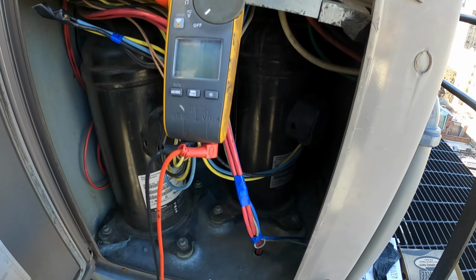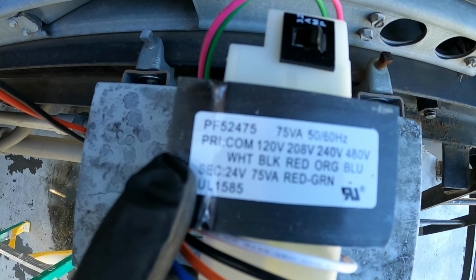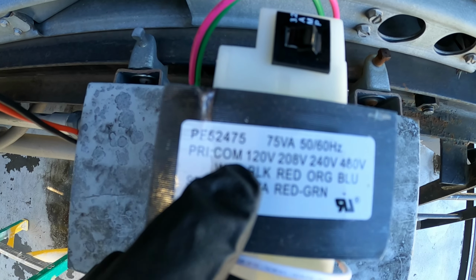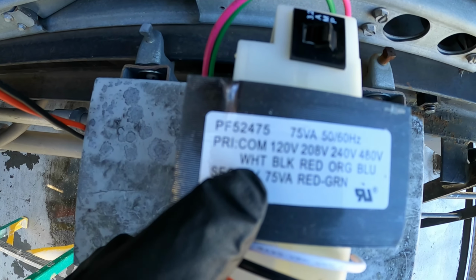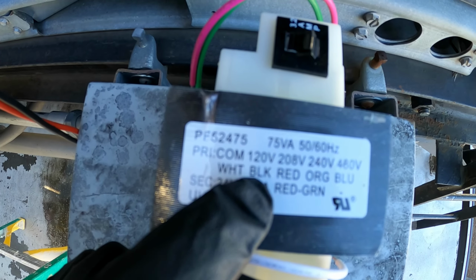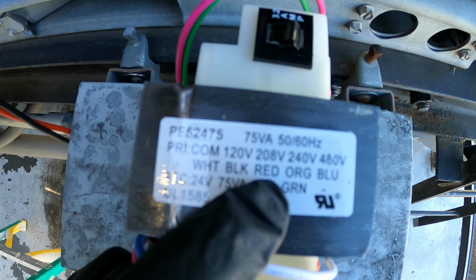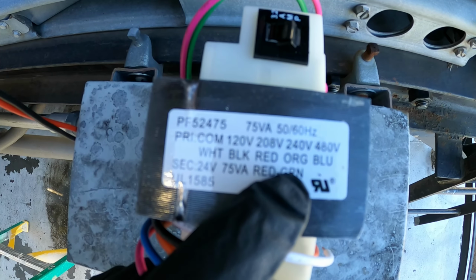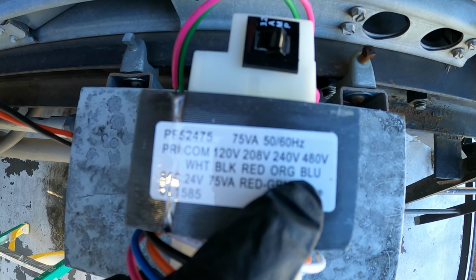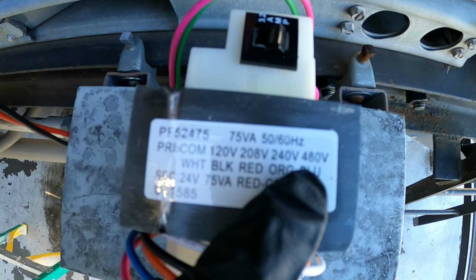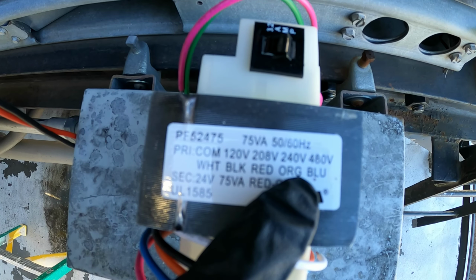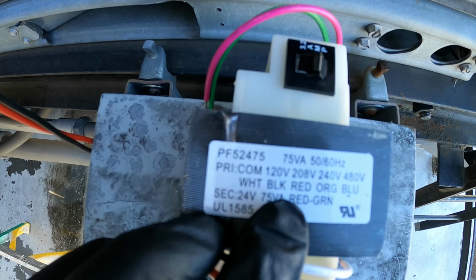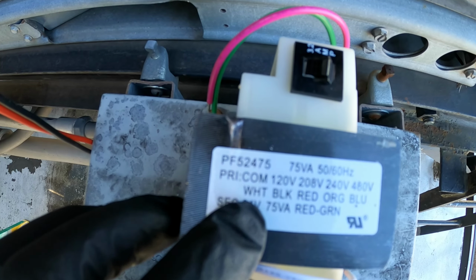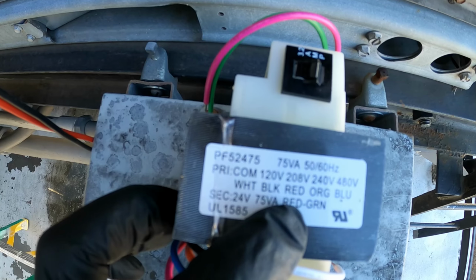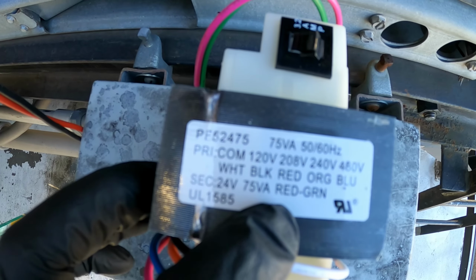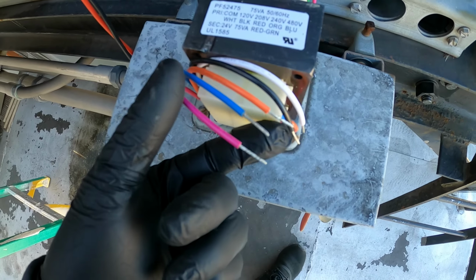Definitely extremely helpful. So since this is a universal transformer, if you guys see, our primary side is common, which is white. We're going to use that. You'll use the black wire for 120 volts. You'll use the red wire for 208 volts. You'll use the orange wire for 240 volts and the blue wire for 480 volts. We're going to cut off and tape off all the other lines that we're not using for our primary. We're using 208 volts. So we're going to use white and red for our primary, and our secondary is red and green, and they're on different sides.